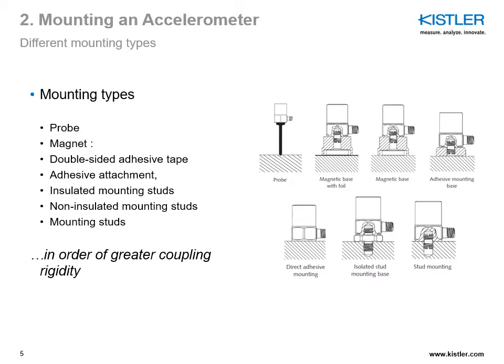Here are the most common mounting types: starting from the probe, then magnetic mounting using a magnet (only for ferromagnetic surfaces), then adhesive mounting — either direct adhesive sensor on the surface or using an adhesive mounting base — and stud mounting. These are represented in order of greater coupling rigidity, meaning stud mounting provides the stiffest coupling and a probe provides the softest.